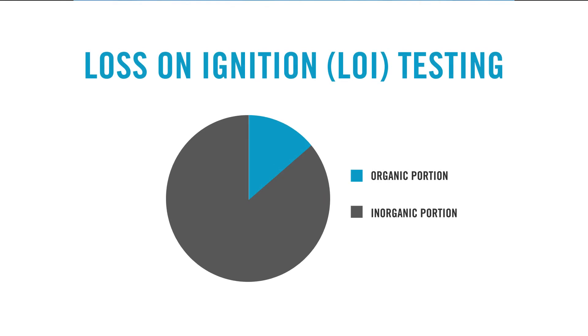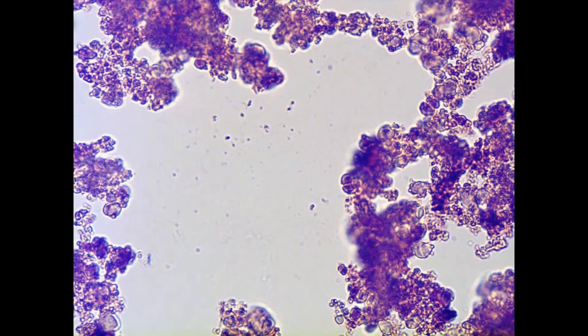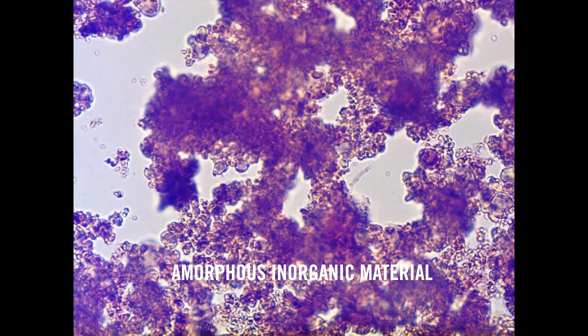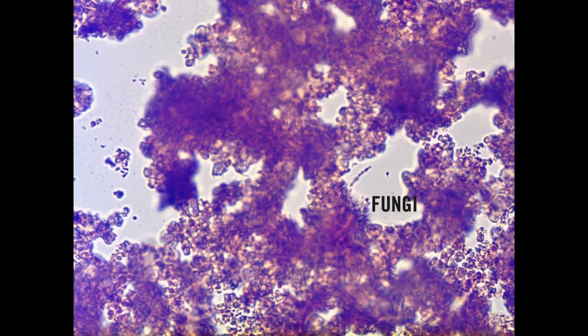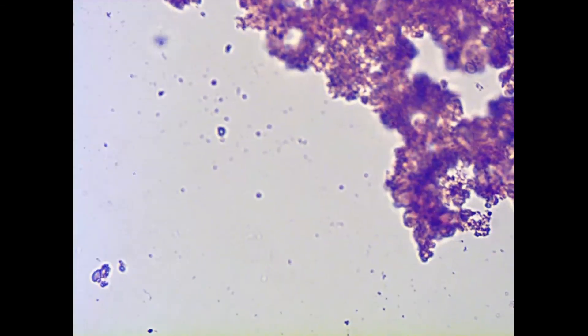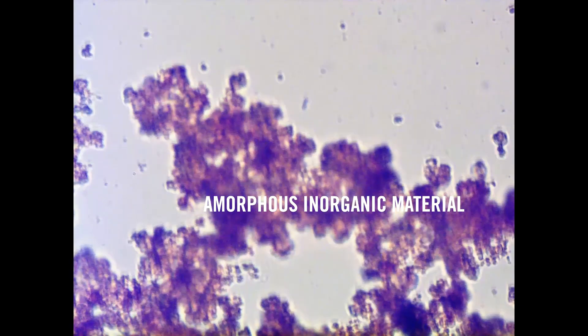When we ran our loss on ignition testing, we found that 72.7% of the foulant was inorganic in content. That means that the bulk of the foulant is inorganic. The client thought that they had a biological fouling issue, and that's what they geared their maintenance procedures towards. So now let's take a look under the microscope and see what biological material we can find. During the analysis we saw mainly particles, which we associate with inorganics, and also amorphous inorganic material, which just means that it doesn't have a crystalline structure. For our organics, we found fungi. But the bulk of the analysis mostly revealed inorganics, which we expected from our loss on ignition testing.